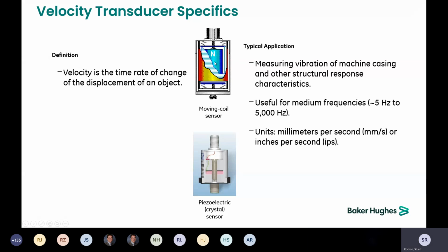Another downside is these are quite often orientation limited. So if you buy a 90-degree plus or minus 10-degree sensor, you have to mount that within plus or minus 10 degrees of 90 degrees. With the piezoelectrics, they don't have the springs, so they don't care at what orientation they're mounted. That orientation basically relates to how the springs are set up inside the velocity pickup to support that coil so that it doesn't touch the magnet and the coil moves freely and gives an accurate reading.